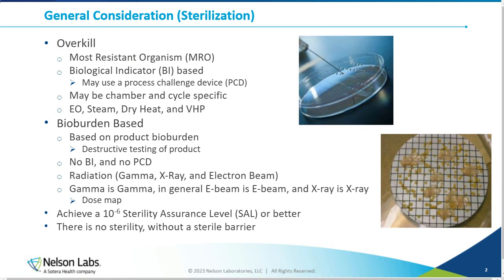So to begin, we have the overkill methods. We generally break sterilization down into two categories. First is overkill, and for that we're going to use a most resistant organism. Commonly in the industry we call that an MRO for short, and that's going to be used to create a biological indicator, again BI for short. And we're going to use that also to sometimes create what is known as a process challenge device, so a PCD. So quite a few differences there, where we're going to be using a most resistant organism, a biological indicator, usually with up to 1 million CFU on it, and we're going to use process challenge devices. With that, your sterilization is going to generally be chamber and cycle specific.